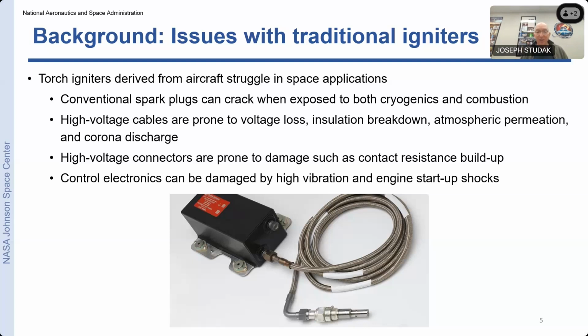The high voltage cables themselves are problematic. They often start off insulating very well, but as you go into a vacuum over time, gas may permeate in, leaving you with insulation breakdown and corona effect. So you can have an intermittent cable that works sometimes and not other times, or works for a while then stops, then starts working again. As you can imagine, a very frustrating situation.